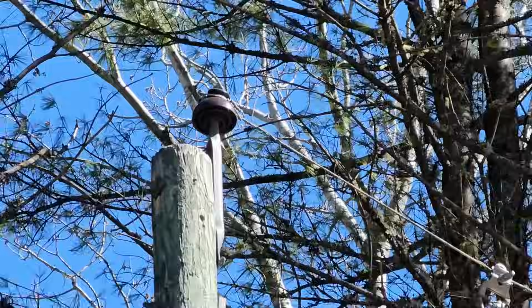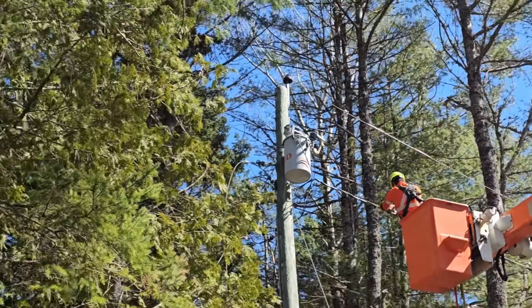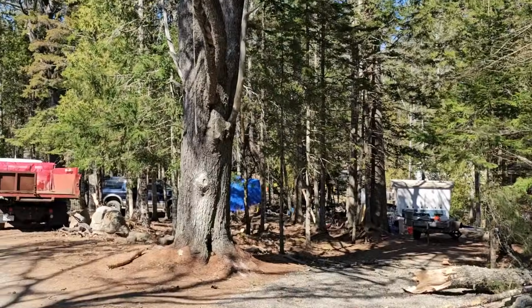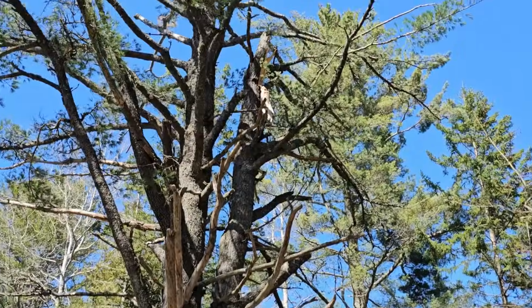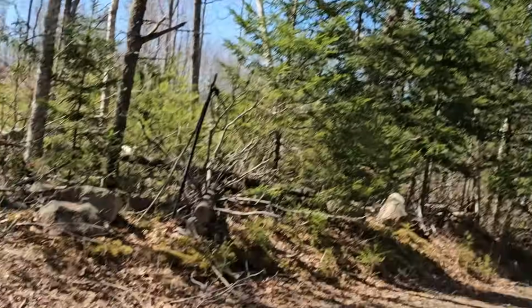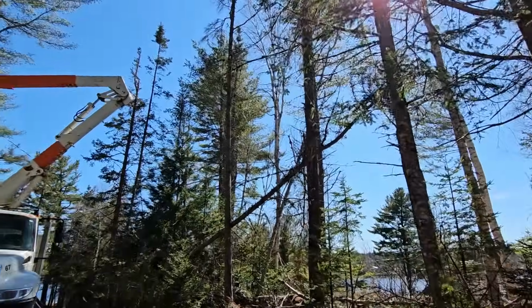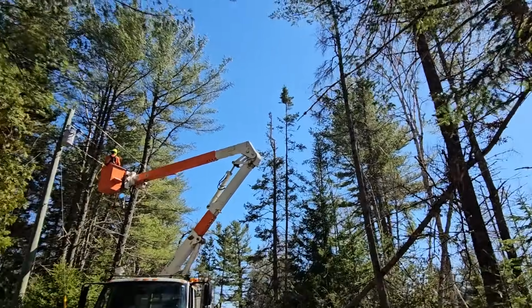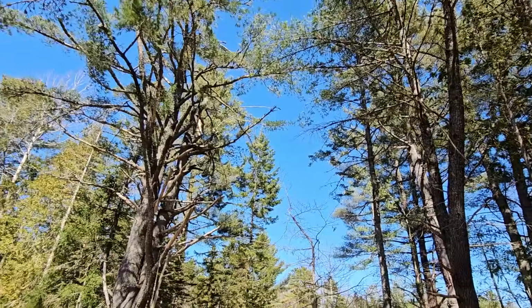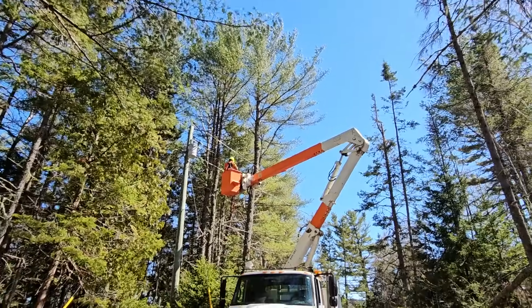See, the primary is just holding on by that tie wire, so that's what we're going to secure with the come-alongs. And the tree that broke came from way up there. There's quite a few trees in the area actually with the tops broke off, so that was another one of our hazards in the tailboard, was to keep an eye out for broken limbs over top. These limbs can easily weigh hundreds of pounds. We don't want nothing coming down on our head while we're working here.